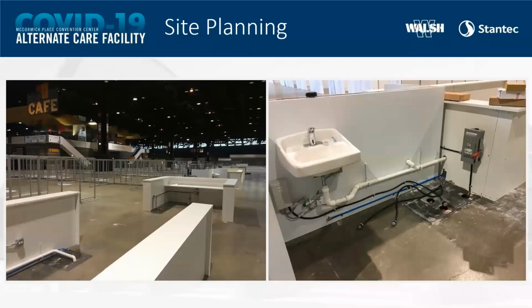It's important to note that the oxygen tank farm, by the way, weighed 334,000 pounds. It was on an elevated slab, so with the work of Thornton Tomasetti, we were able to structure that slab. Also the medical gas system was fully certified. What we have depicted here is the placement of the nurse stations as the driver for the placement of the modules. We also show the sinks, which were important because we placed these within proximity of the floor boxes, but we discovered not every floor box had water. So we had to make adjustments. Not only that, they did not have hot water, so we had to include localized heating for the water systems.